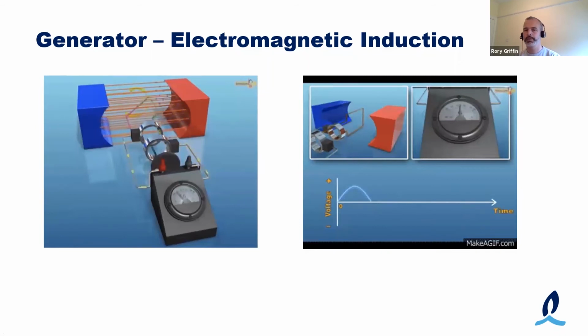And then from there, as the mechanical power increases on the gas turbine, initially only, you'll start to open up a power angle. So I'm trying to get this right in the camera like this. As the angle between the rotating field of the rotor and the grid starts to open up more, you actually push out more power then.